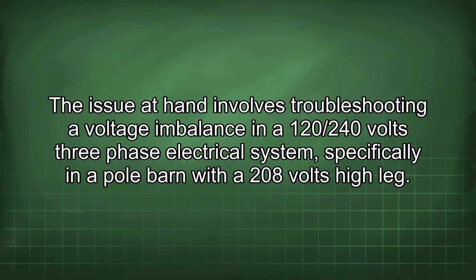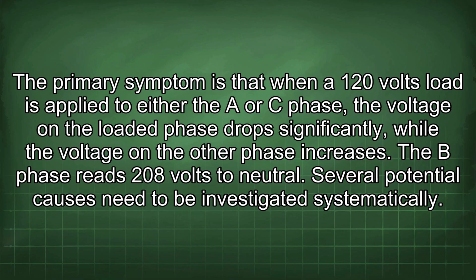The issue at hand involves troubleshooting a voltage imbalance in a 120/240 volts three-phase electrical system, specifically in a pole barn with a 208 volts high leg. The primary symptom is that when a 120 volts load is applied to either the A or C phase, the voltage on the loaded phase drops significantly, while the voltage on the other phase increases. The B phase reads 208 volts to neutral.